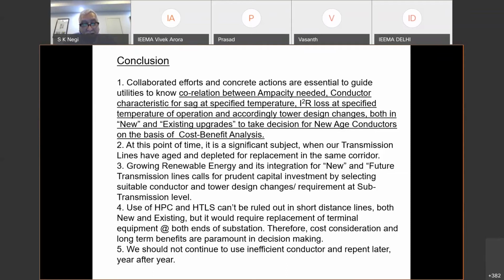So in conclusion, the last point I will say is that we should not continue to use inefficient conductors like ACSR Moose and then repent later, year after year. I find this story of ACSR Moose going on since 400 kV lines were established, from a young age up to 2008. Somewhere around 2008 this new age conductor concept came, but still after two years I find there is a need for discussion, and there is no discussion. Why? Because utilities and people don't understand that the selection of conductor calls for a change of design. There is nothing to fear about that. And this change of design and modification is required.